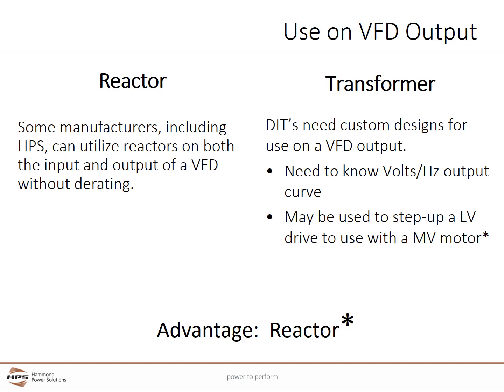When using a drive isolation transformer on a VFD output, you must know what the volts to hertz curve is that the VFD will be using with the motor. This is especially true if the VFD will exceed 60 Hz, start at 50 Hz, or spend long times in low frequency situations where the VFD voltage boost is used to increase available torque at low speeds. Differing volts to hertz curves can cause additional DIT heating and failure. DITs must always be custom made for any VFD output. Reactors aren't as sensitive to differing volts to hertz curves, but it's always good to check the reactor with the manufacturer if the VFD will simulate output frequencies above 60 Hz. In this case, the advantage goes to the reactor.